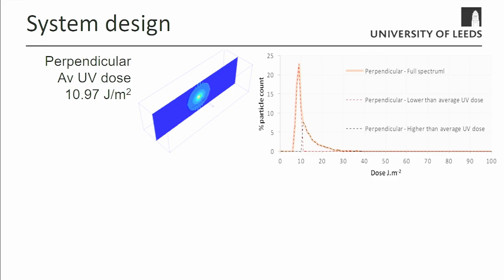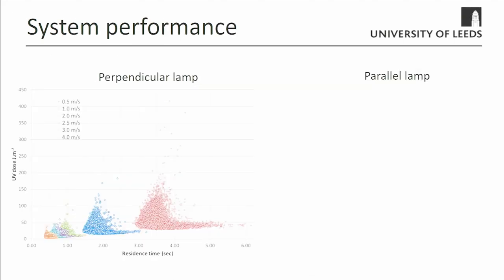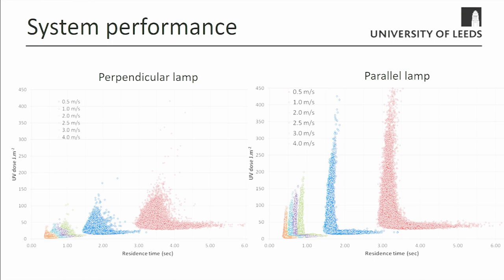We can also model the lamp in a different orientation — parallel to the duct rather than perpendicular — and we get a different average dose with exactly the same lamp just by changing orientation. We get a slightly different distribution: some particles with very high doses have low residence times and go close to the lamp, while others with very low doses are a long way from it. Without the modeling, you can't unpick this at all. It's not 100% perfect, but it tells you something about what you should be looking for and how the system works.